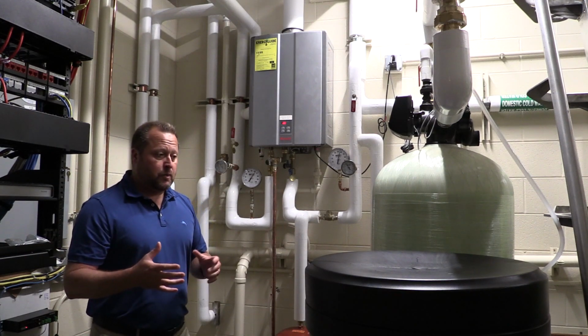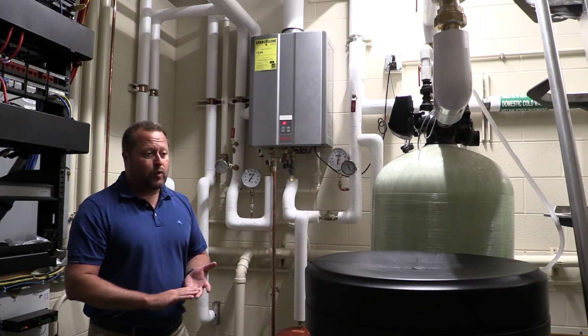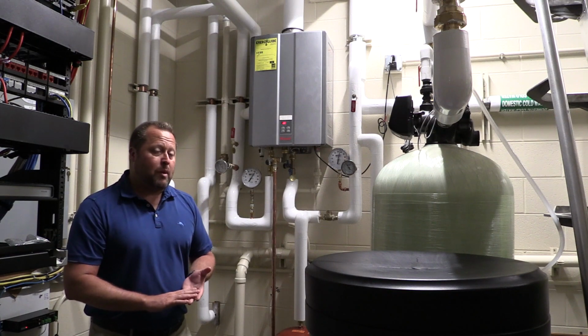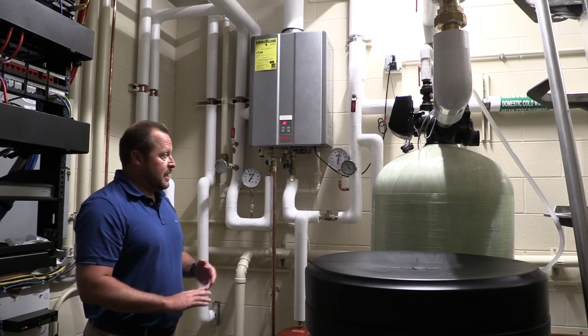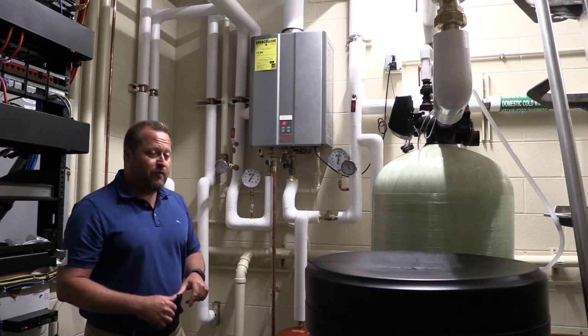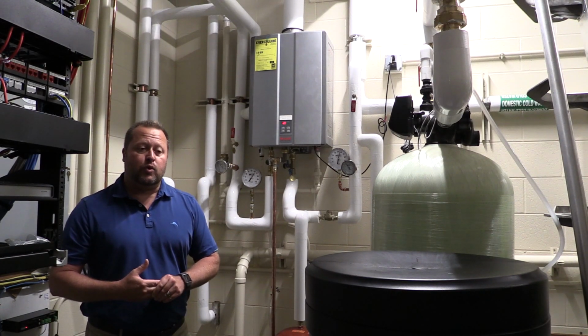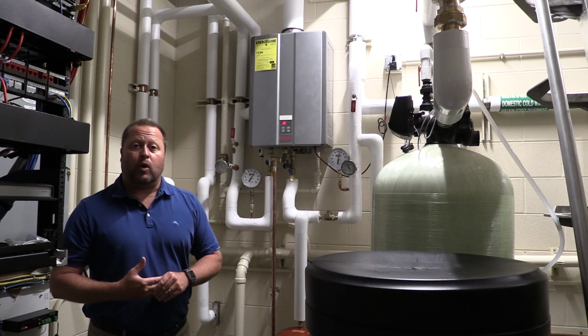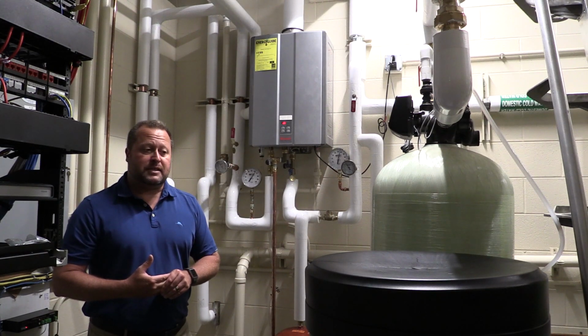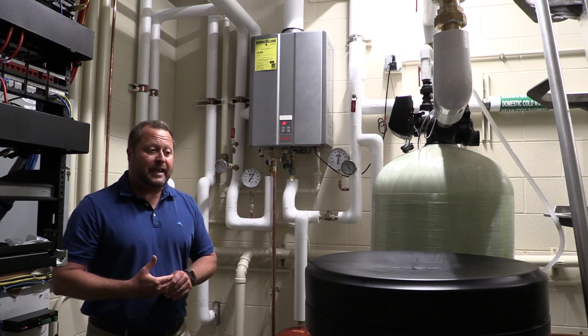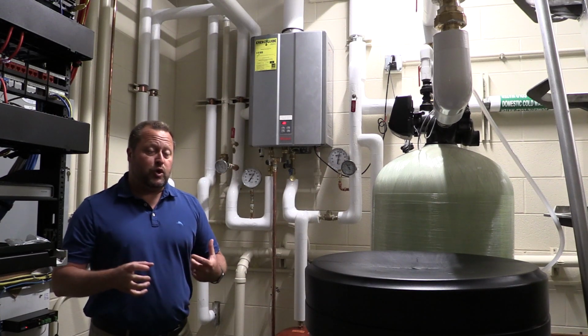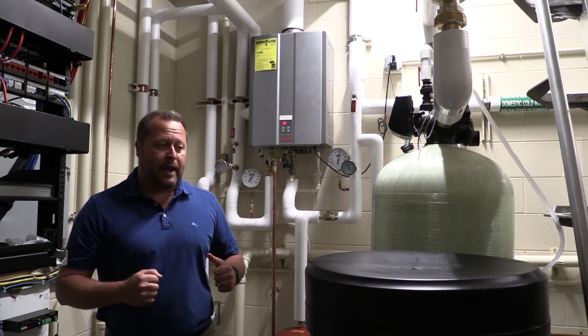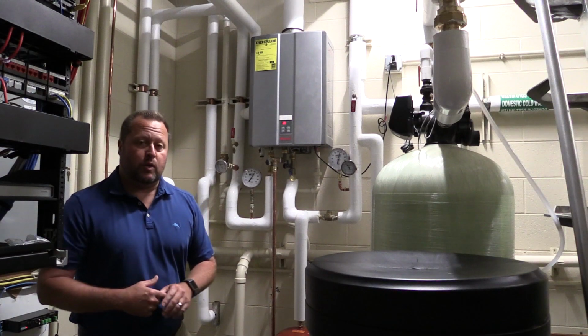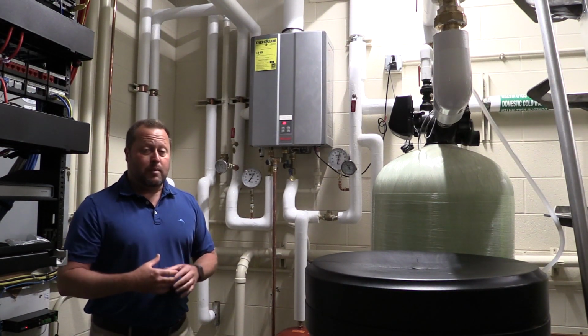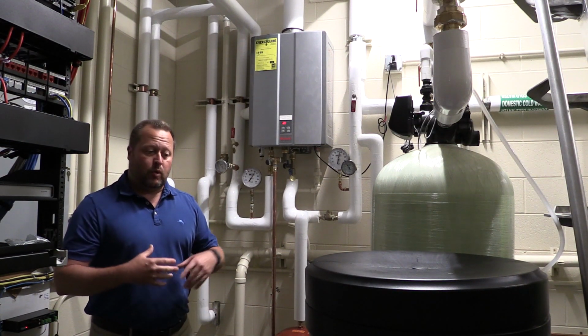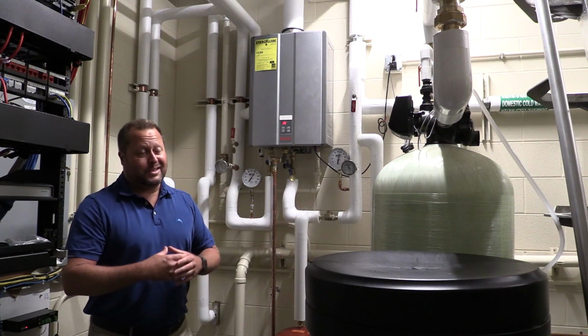So I mentioned this earlier. They recommend it once a year on softened water. If it's hard water, probably should do it more like twice a year. And that's isolate the heat exchanger and run 4 gallons of distilled white vinegar through the system, the heat exchanger, for an hour. And that should, in essence, take care of the heat exchanger and clean it out. Do not do multiple uses on that vinegar. Once it's done after that hour, dispose of the vinegar, because it will not take on any more scale, because it only loads up so much and then it's exhausted.